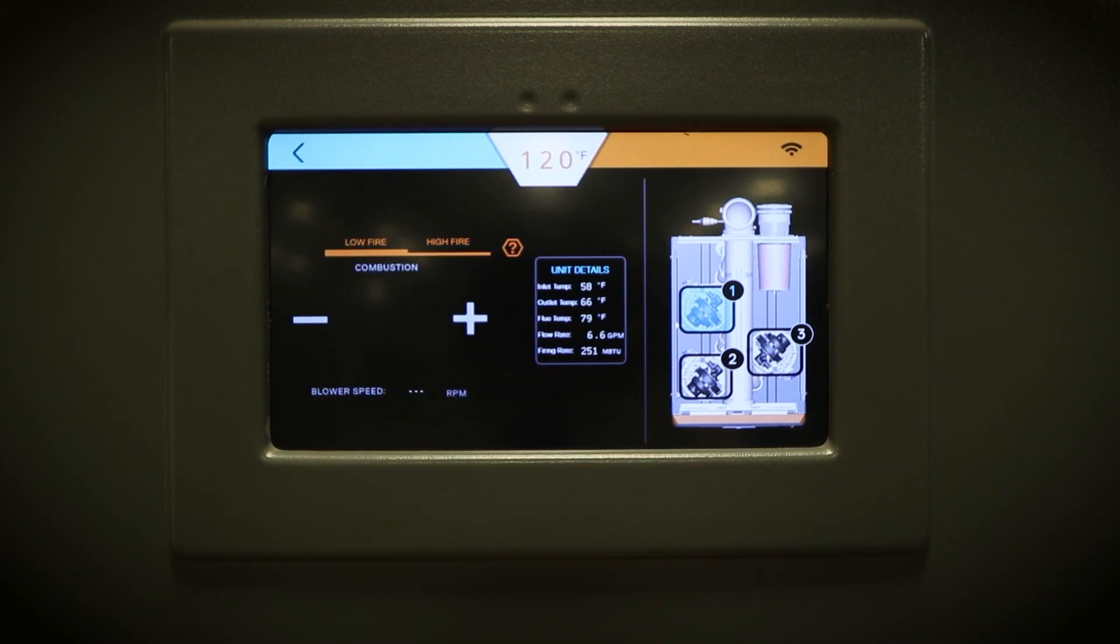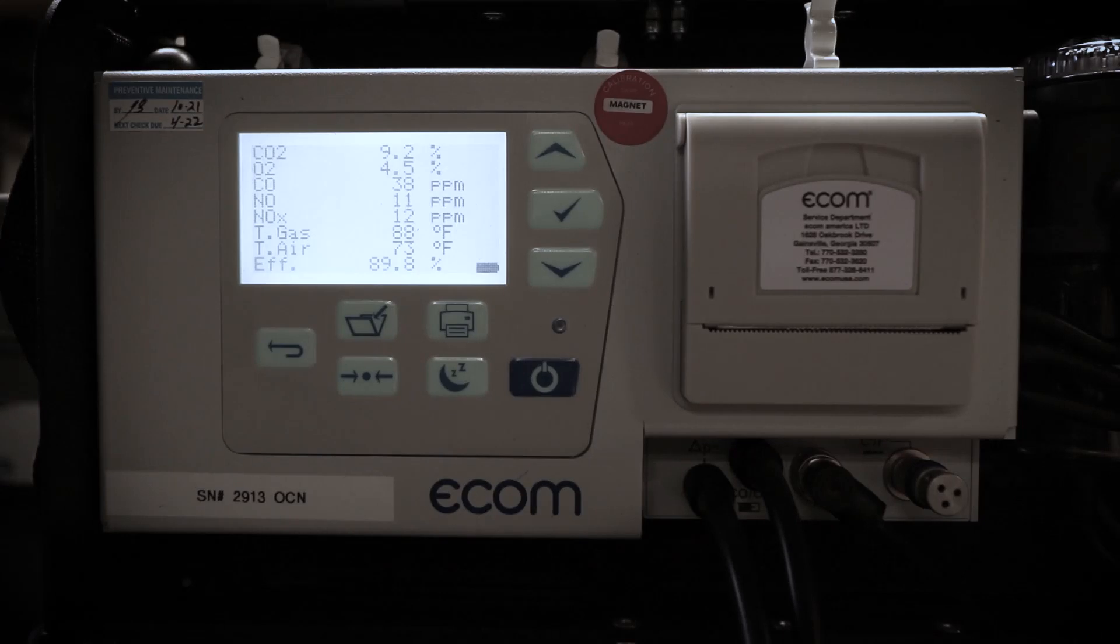Allow the unit to enter low fire. For low fire, the CO2 needs to be between 9.1 and 9.3% on natural gas units. On propane units, the CO2 needs to be between 10.1 and 10.5%. Additionally, make sure the CO level is less than 60 parts per million.